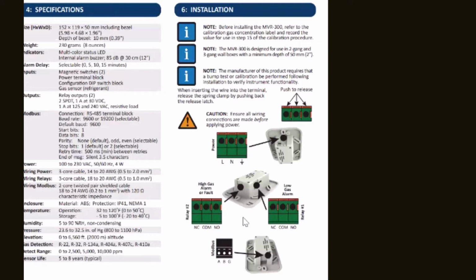How? Well, okay. So the way these work is the controller is connected to each one of the MVR-300s through Modbus and through the network that we're going to go through. So that connection's already done. Your low alarm and your high alarm can be used for other things. Okay. So yeah, it makes sense to me actually. The more I think about it, we're talking about 6 foot of probably 20 gauge two conductor coming out of that MVR-300 to our patient station, and now we have an alarm right at the nurse's station. Sure. No, I think that's a reasonable solution.